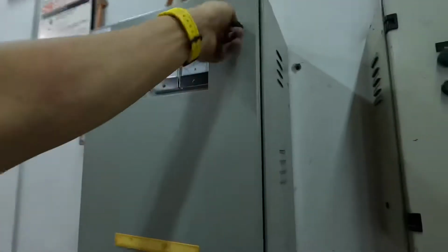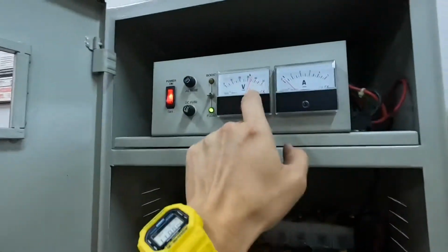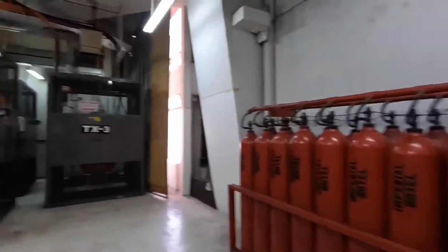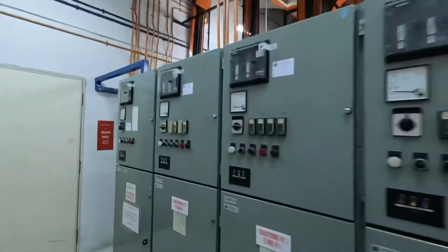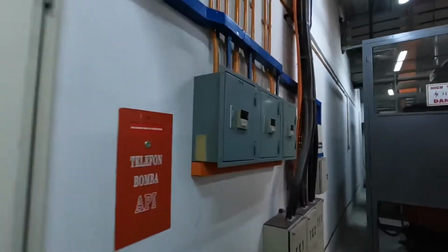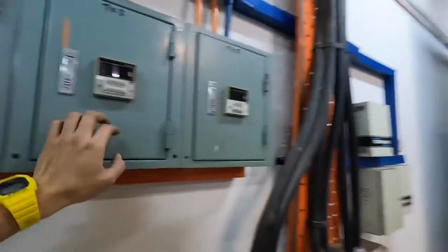If let's say there's some partial discharge ongoing, and do make sure the room temperature is okay, not excessively hot. Make sure the room is dry, no moisture, no water flooding, no water ponding, because even though it doesn't short circuit the electrical system, it could also cause the room humidity high, thus condensation can happen. Okay, this is the tripping unit battery. Make sure voltage is above 30 volt DC. The temperature controller here is faulty, will be replaced soon.